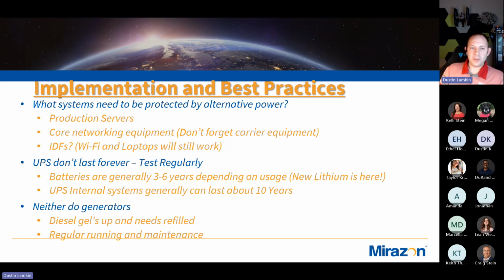Another best practice, these UPSs don't last forever. Old lead acid batteries generally last 3 to 6 years depending on usage, heat, and other factors. We need to maintain them properly. Now the new lithium batteries from APC and Schneider claim 10 years with much better longevity. So we try to place those where they'll be most beneficial for the business, since they're more expensive, but if you only have to replace them once every 10 years instead of every 3 to 6, it can really pay off.